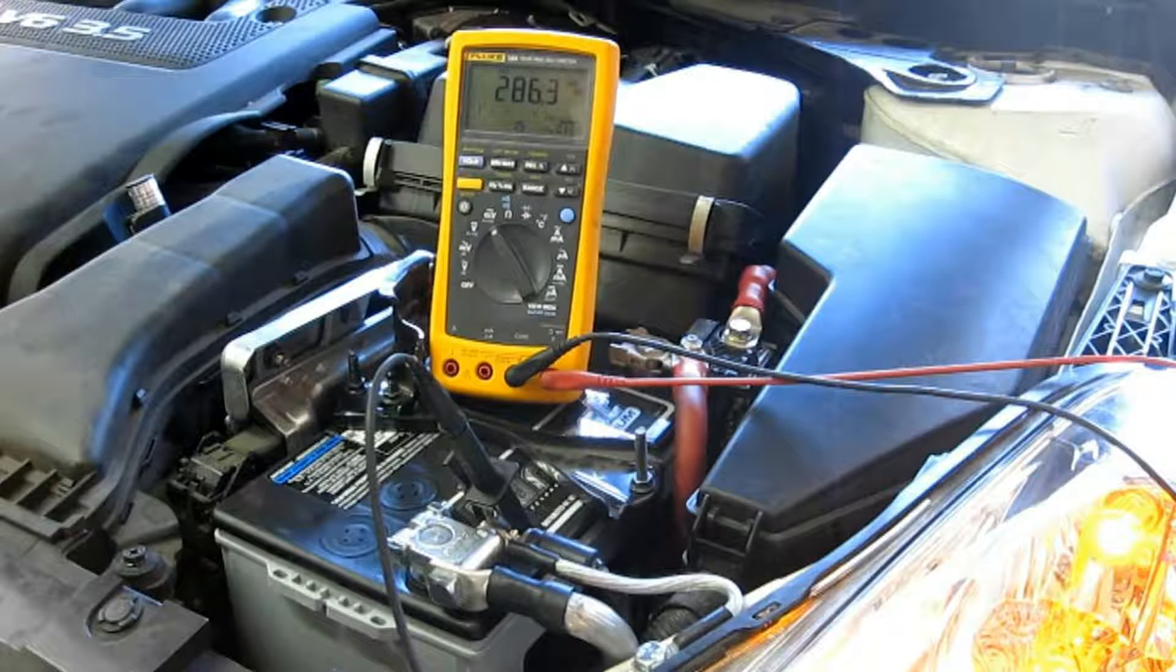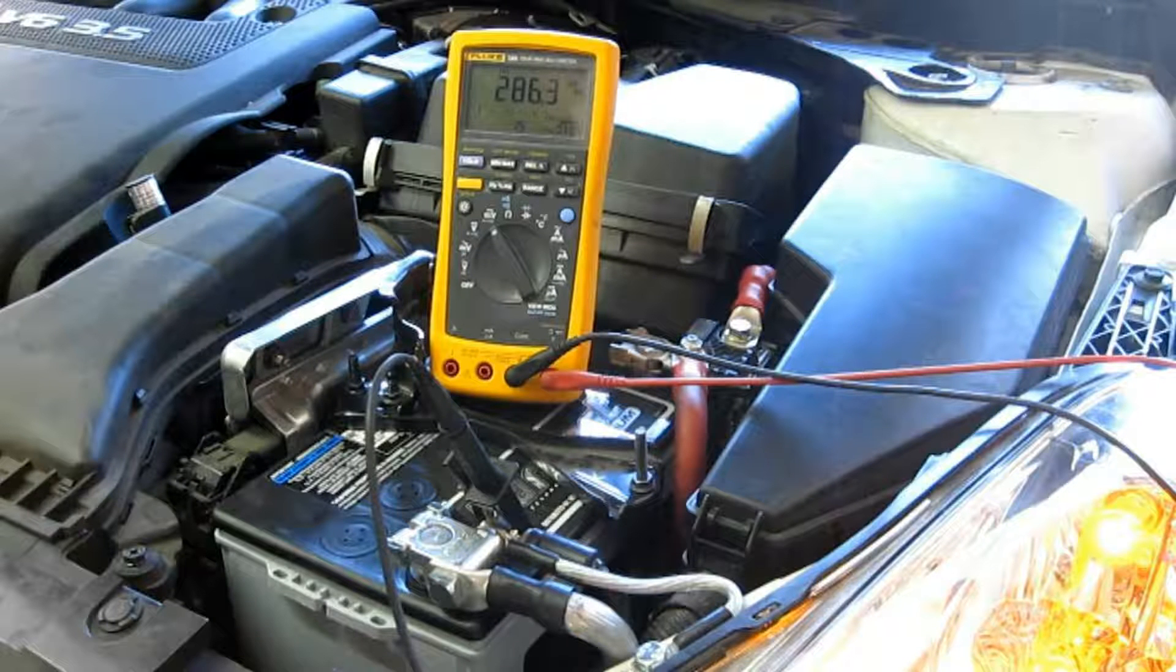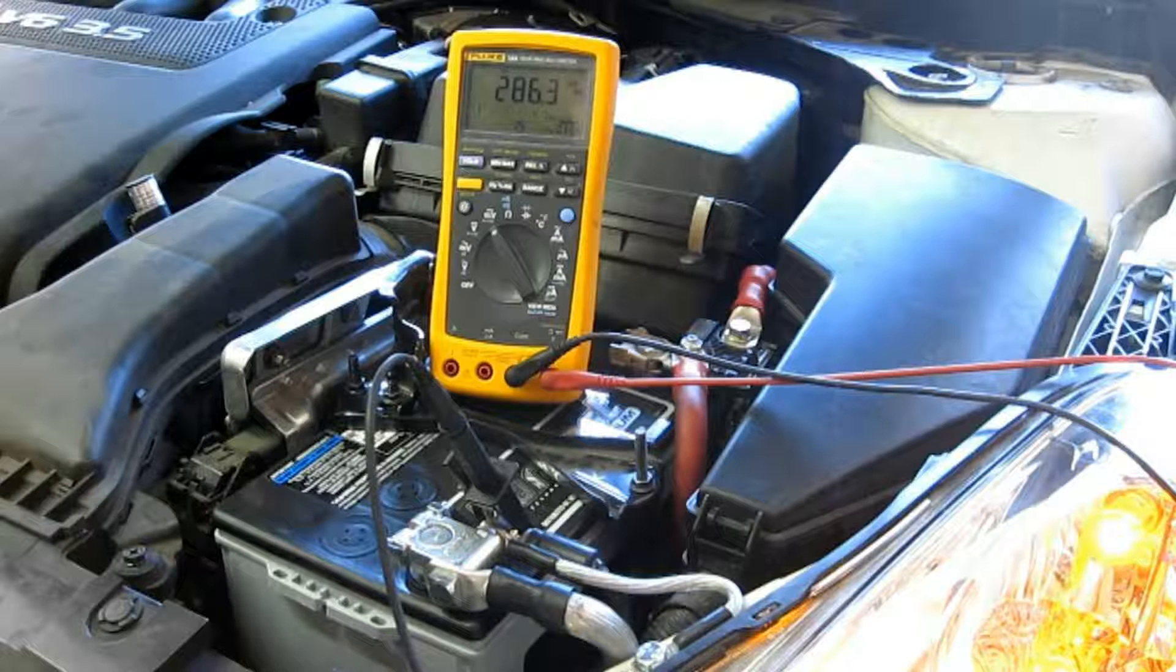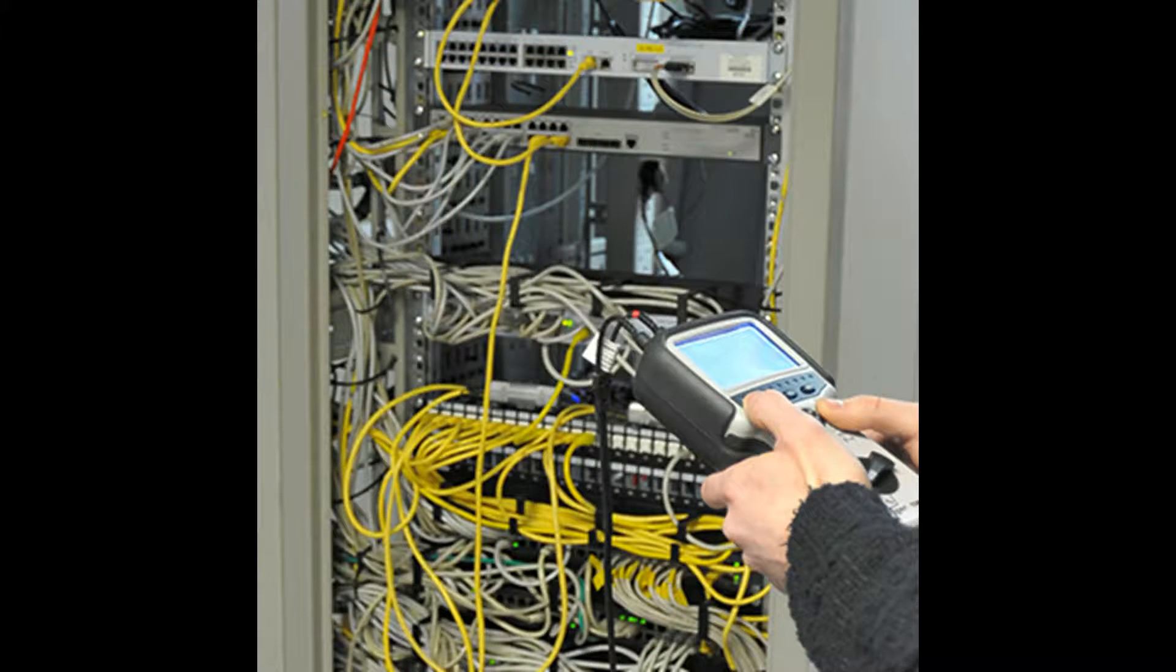Now, the most common method of troubleshooting is to use a multimeter. It's a simple device that easily tells you if you have an open or a short in a wire, but it will not tell you where that open or short is. If you'd like to learn how to use a multimeter, please see my video on how to troubleshoot a two-wire system. Anyway, now that you've found the problem wire, remove the multimeter and hook up your TDR.